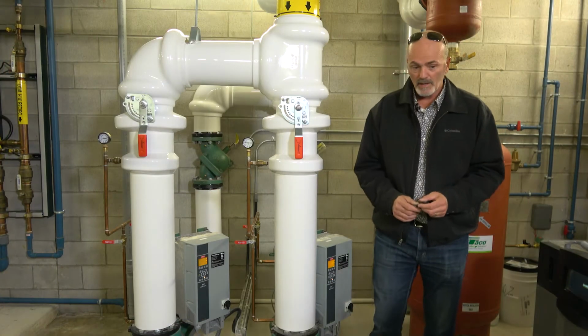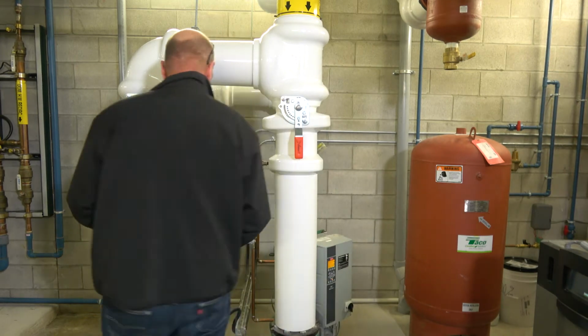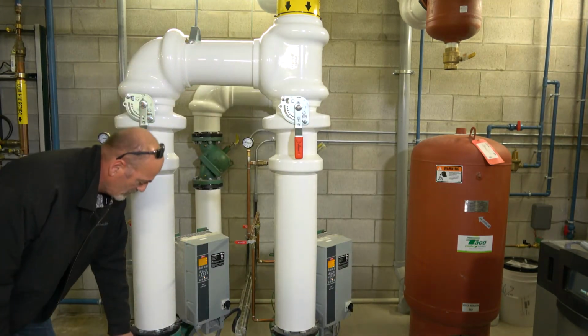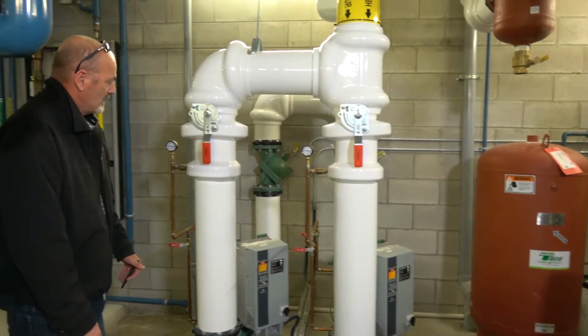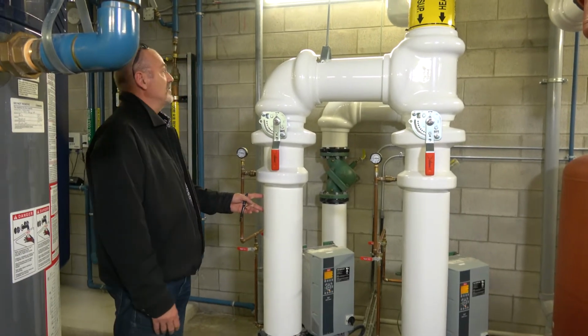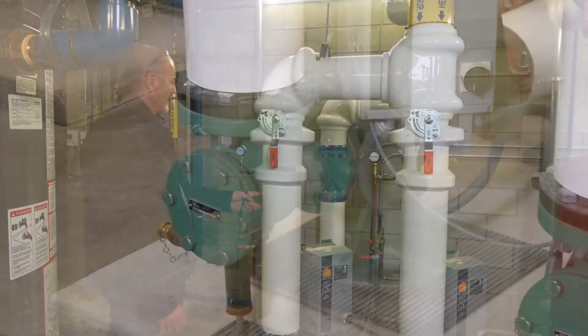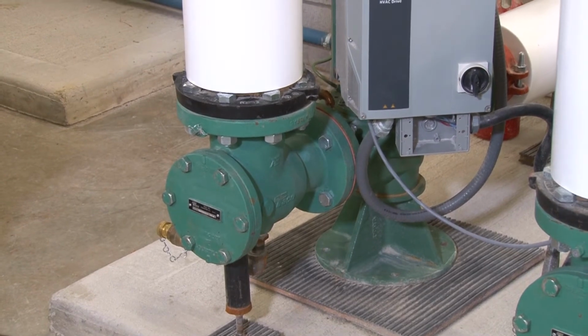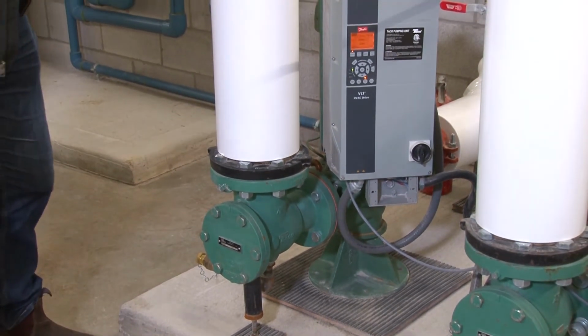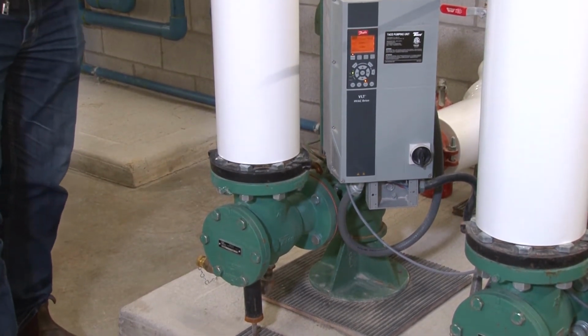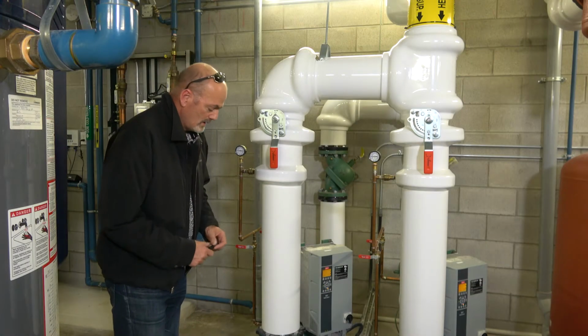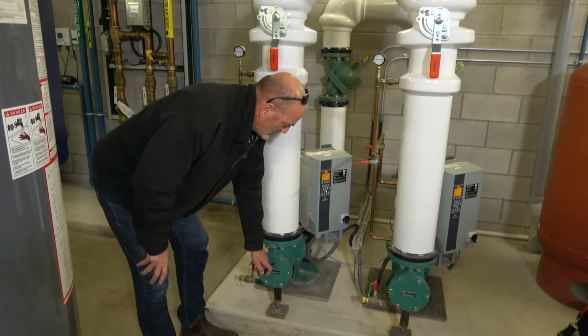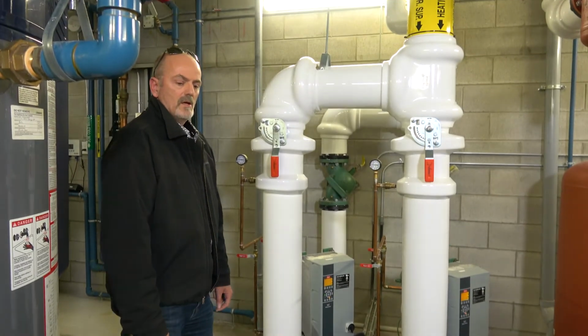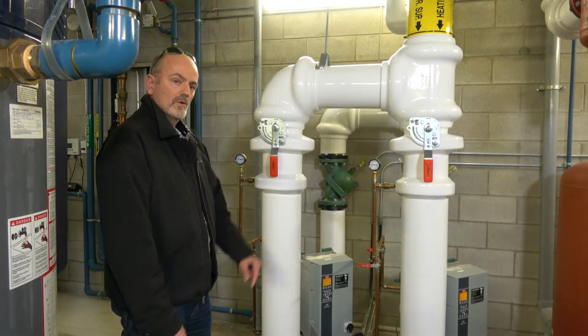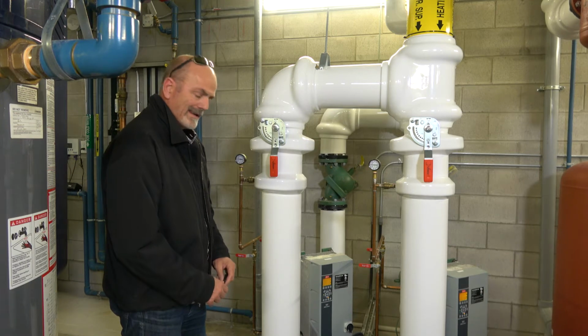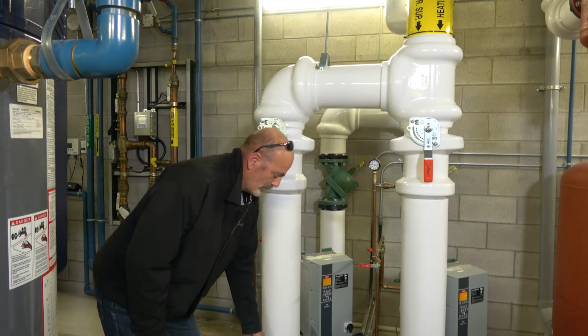So each pump also has what we refer to as a suction diffuser. That's this here. It allows you to go from a pipe size, which in this case might be, was it 4-inch? 3-inch, down to the pump inlet, which could be a 2.5 or a 2 or maybe a 3. But more importantly, this device is meant to maintain what's known as laminar or nice straight flow into the inlet of the pump when you have a tight turn like this.